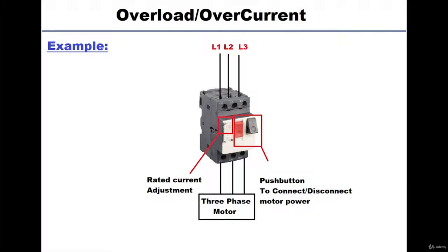And you might ask, is this fast response due to magnetic or thermal characteristics? Well, here it is due to the thermal characteristics that are sensitive in this case. However, this one also has magnetic protection, and as with the circuit breaker, it's rated at between 6 and 10 times the rated current you adjusted.